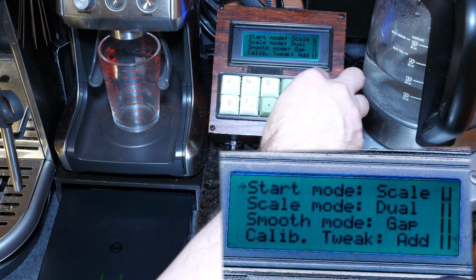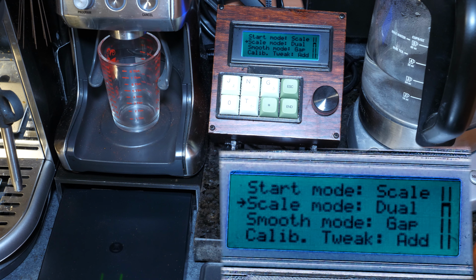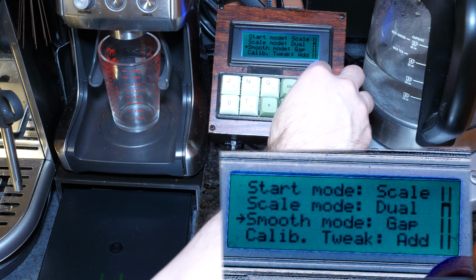You can switch between what it's at now, which is showing the scale on the left, this secondary scale here, and the primary scale here. You could also switch it to automatically switch between them, whatever's got weight on it. Guess I'll go back to dual mode. You can choose the smoothing algorithm used to smooth out the weight sensor measurements to give you a nice clean measurement of the weight on there so it doesn't bounce around, but you've got some options there.